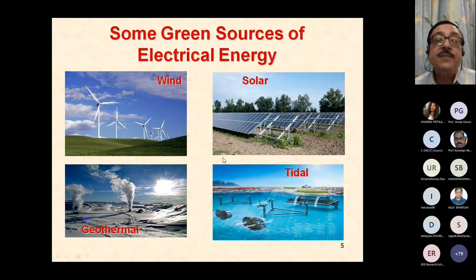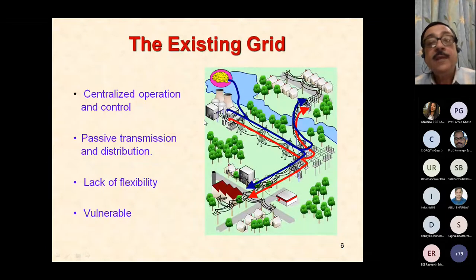So these are the typical sources of green energy. Now, this has been the existing grid as it has been till a few years back. We had a central generating plant somewhere down here. From here, we have the typical transmission line, and then it comes to the distribution system, and the power is distributed to different consumers as they are. So it's a passive transmission system and distribution system. And in case of any interruption of power from the main station or from the transmission line, things go dark, you don't have the power to any of the consumers, and everything is coming from a centralized operation.